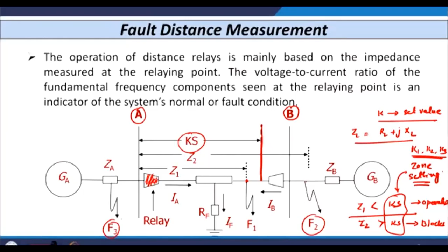So we have K1, K2, and K3. These are the three zone settings of the distance relay, one indicated by zone 1, second zone, and third zone of the distance relay. And sometimes it may be possible that a fault occurs on the reverse side of this relay. The relay then measures an impedance that is not positive, it is negative. It actually falls in the third quadrant, so the relay is not going to measure the correct value, it measures the negative impedance and hence the relay does not operate.